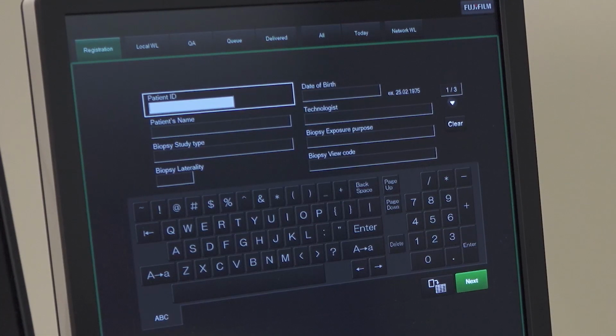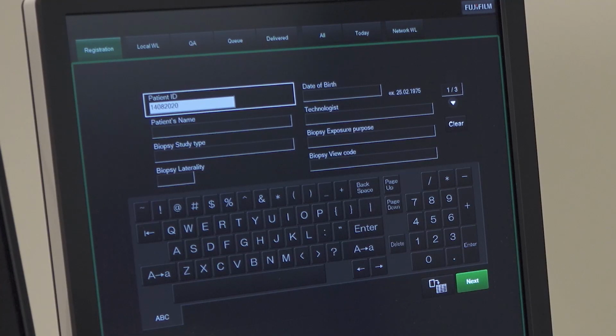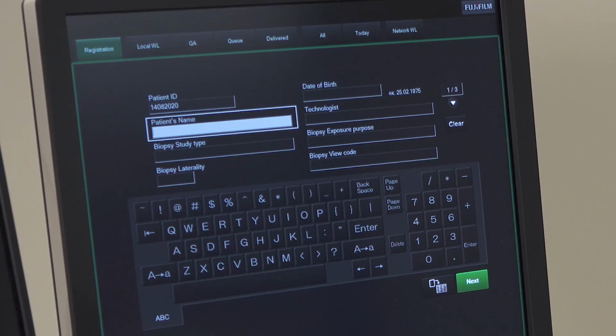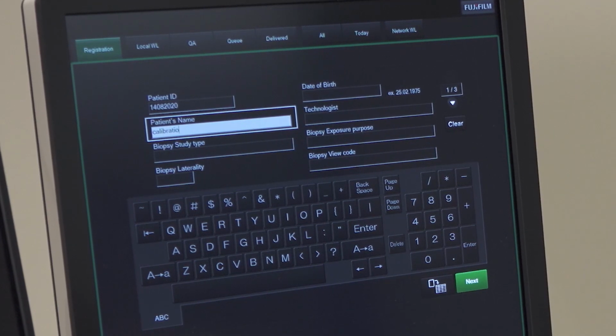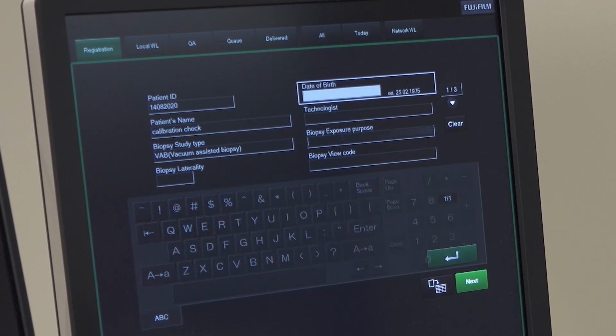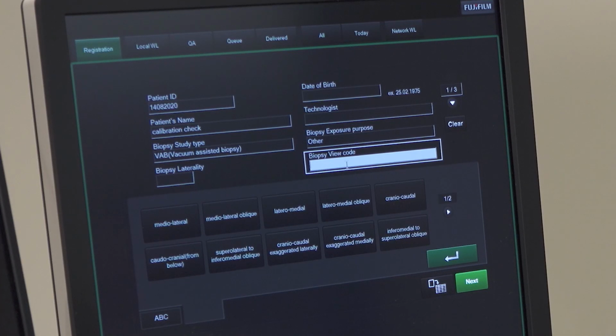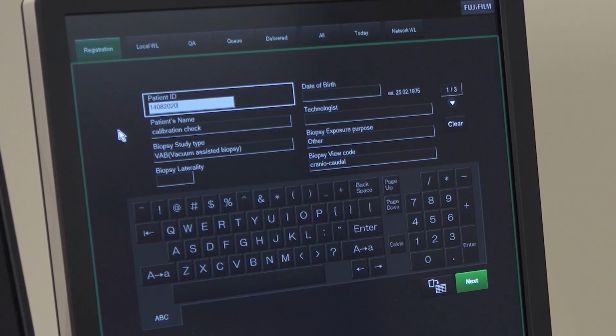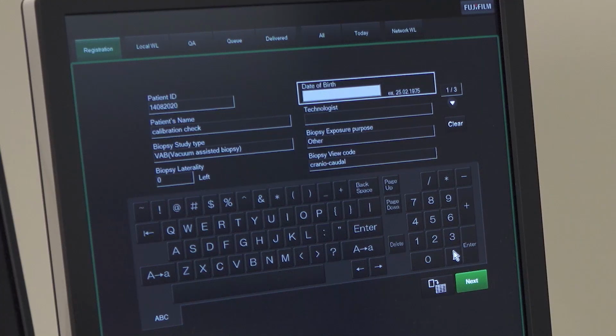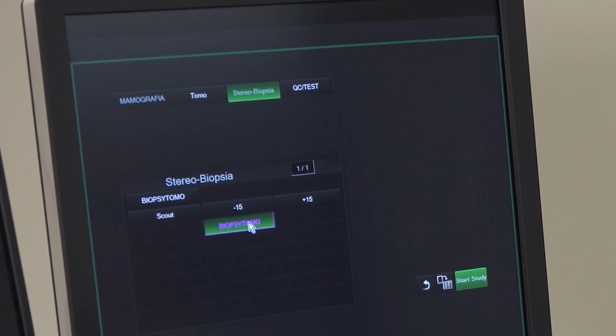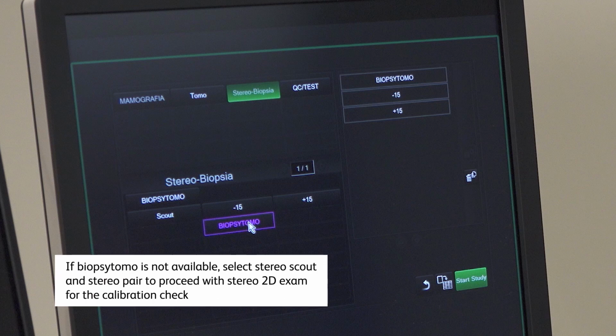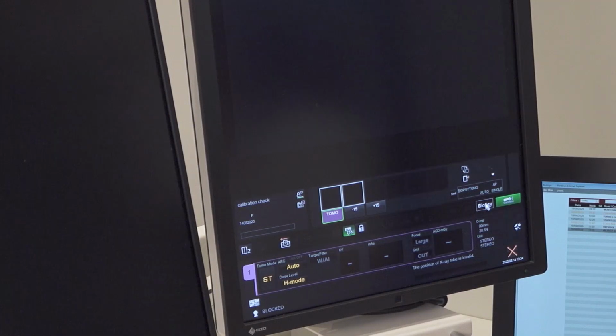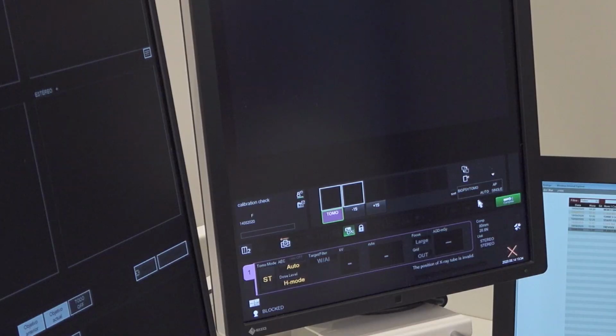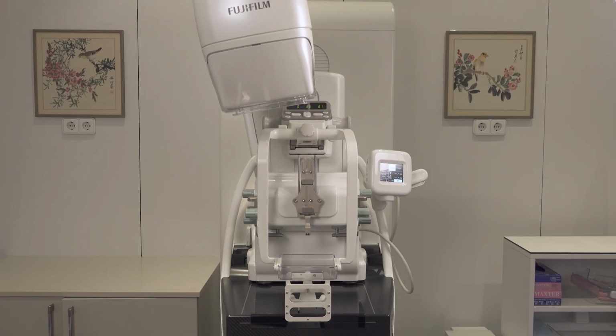Register the calibration check patient information as required and start a biopsy exam to run a calibration accuracy check. Select a biopsy tomo exam. Once the study is started and the biopsy button has been clicked, the system is ready for exposure. Press the exposure button to complete the biopsy tomo sequence.